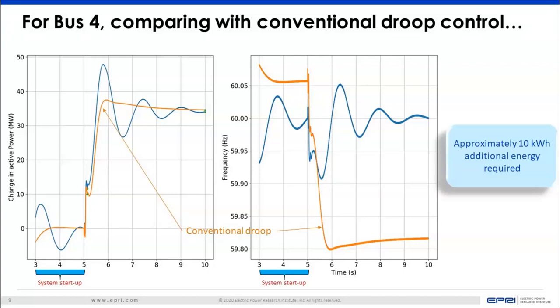And in fact, if you calculate the energy under the curve for these two scenarios, from the time of the event to the time of settling, the additional energy required for the blue curve is only 10 kilowatt hours. So for a small incremental energy being injected by the inverter-based resource, one can achieve much more superior frequency control in this kind of setup.